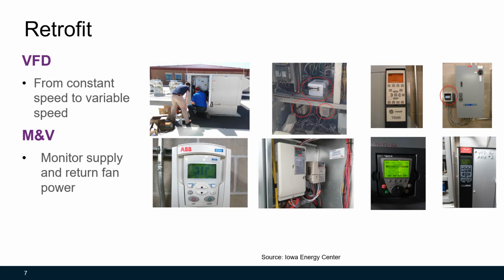For a constant volume system, you do need to add VFDs to these supply fans to change them from constant speed control to variable speed control. Here are some photos of the VFDs at these sites. We added power monitoring equipment on these VFDs to monitor supply and return fan power.